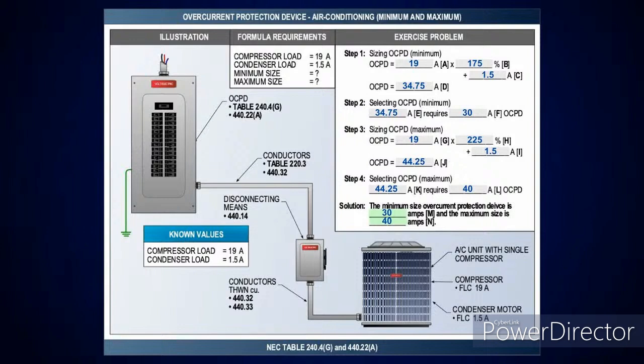I mean, just so everyone understands what we're talking about, let's say you have one of these HVAC units, and you decide you want to put a 30 amp overcurrent device on, say, whatever your minimum circuit ampacity is, 40 amps, whatever. You can do that. That's not a problem. But if that minimum calculation comes down to, say, 35 amps, and all of a sudden you get a breaker tripping, then you know that you can increase that overcurrent device and stop that nuisance trip. So that's the reason the minimum is there, so that you can understand.